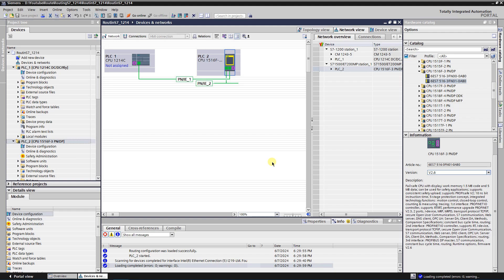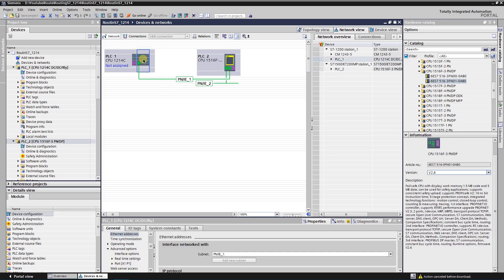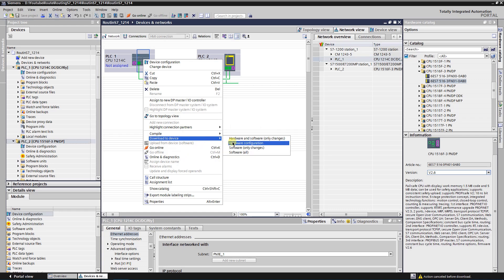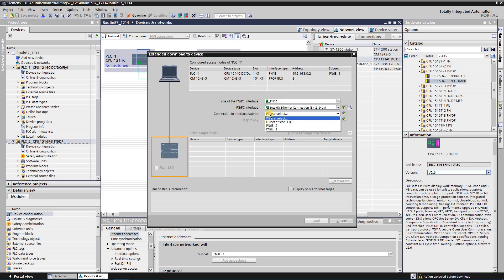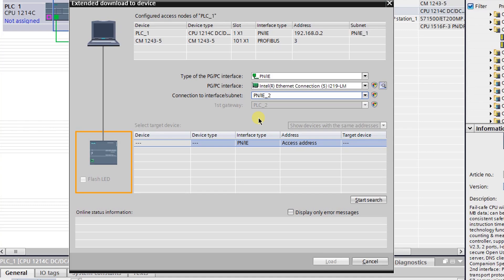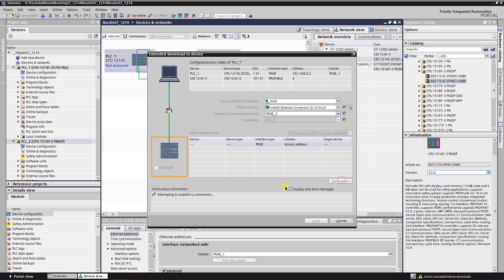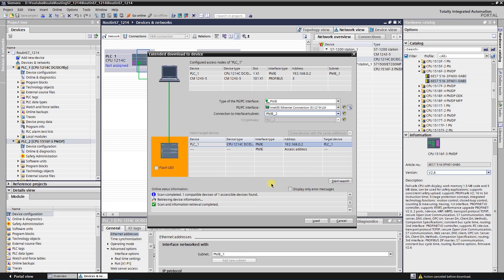S7 routing setup is sent to the second CPU. Now you can download the hardware configuration to the first one. Select your first CPU, right-click on it, select Download to Device, and then select Hardware Configuration. Select PNIE2, as the PG/PC is connected to that subnet. TIA Portal adds PLC2 as gateway automatically. Click on Start Search. The first PLC that is in the PNIE1 subnet has been found. Select it, click Load, follow further instructions, and wait till the process is finished.